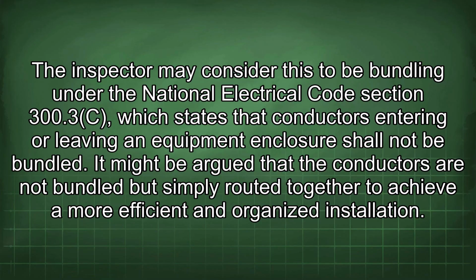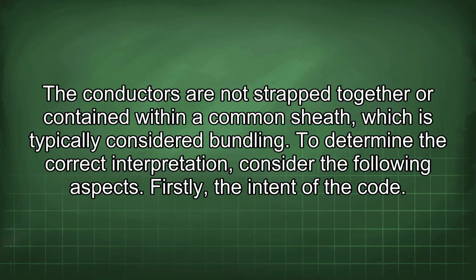The inspector may consider this to be bundling under National Electrical Code section 300.3c, which states that conductors entering or leaving an equipment enclosure shall not be bundled. It might be argued that the conductors are not bundled but simply routed together to achieve a more efficient and organized installation. The conductors are not strapped together or contained within a common sheath, which is typically considered bundling. To determine the correct interpretation, consider the following aspects.